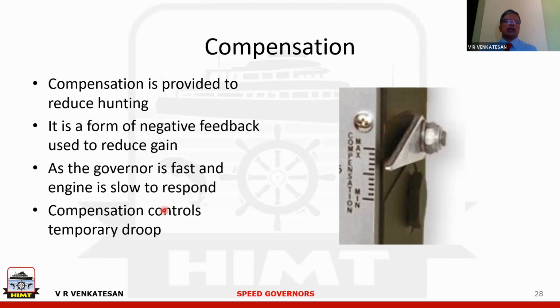So what we say is that compensation is for handling a different problem. This is called temporary droop. Temporary droop means, as the load is increased, how much is the speed coming down? You don't want the speed to come down too much. At the same time, if you try to restrict it too much, then it will be hunting all the time. So another way of telling: compensation is for controlling the gain of your governor, or for controlling the sensitivity of the governor.